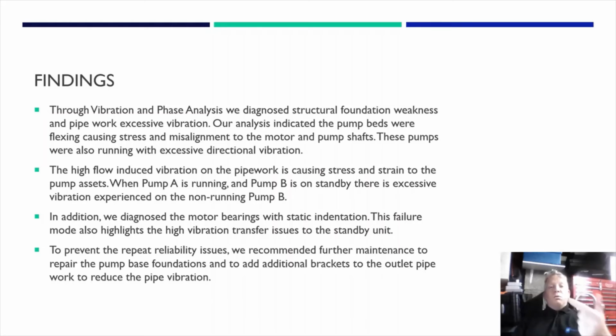So also one point to note on the pumps is when they come out, we had flow induced vibration, because when they designed it, in theory it might have worked, but in practice sometimes things don't. They had short bends, so as the water would go around the short bend, we get flow induced pipework strains, and obviously the pipe was moving like that.